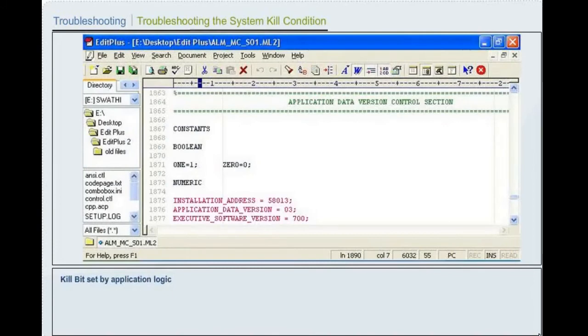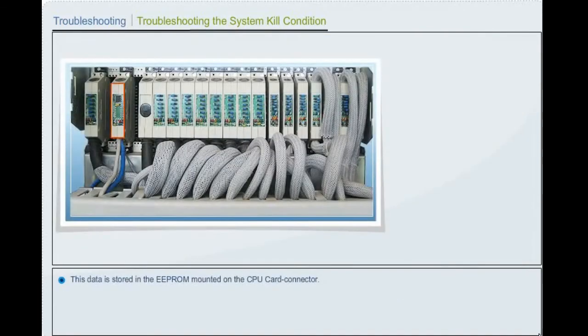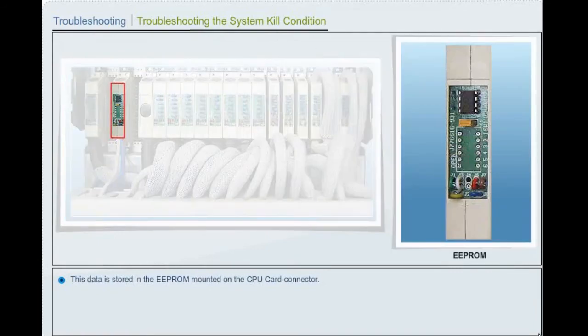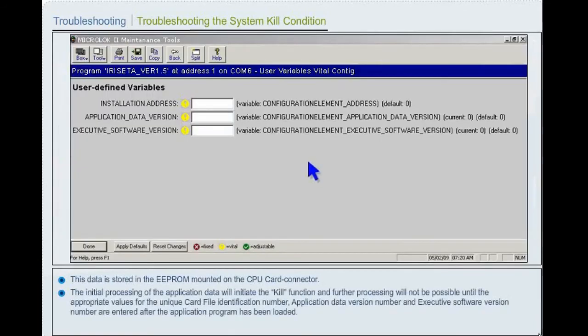Troubleshooting the system kill condition. Step 1. Kill bit set by application logic. Each card file is given a unique card file identification number in the application software. This data is stored on the EEPROM mounted on the central processing unit card connector. The initial processing of the application data will initiate the kill function, and further processing will not be possible until the appropriate values for the unique card file identification number, application data version number, and executive software version number are entered after the application program has been loaded.